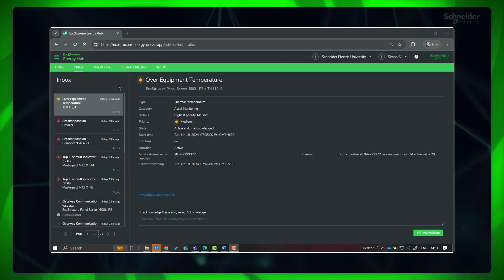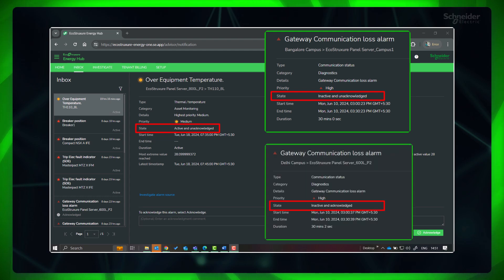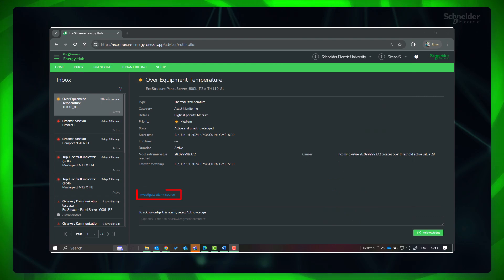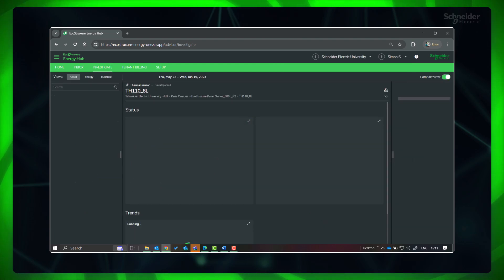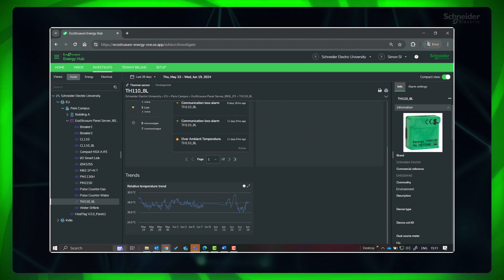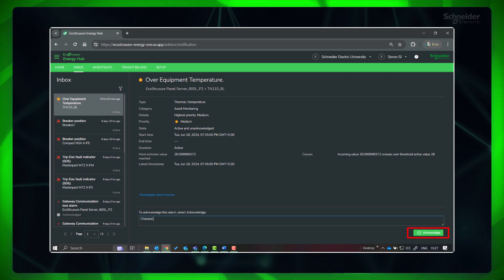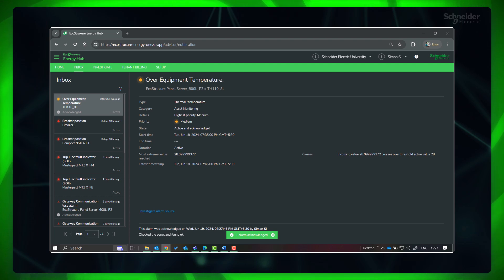Alarm information will show the category, type, detail, priority, and state, along with the start and end times and duration. Alarm state could be active or inactive and acknowledged or unacknowledged. Click on Investigate Alarm Source to go to the location where the alarm originated and analyze the details. You can acknowledge an active or inactive alarm. When you acknowledge an alarm, Energy Hub records the username of the logged-in user, the date and time of the acknowledgement, and an optional comment.